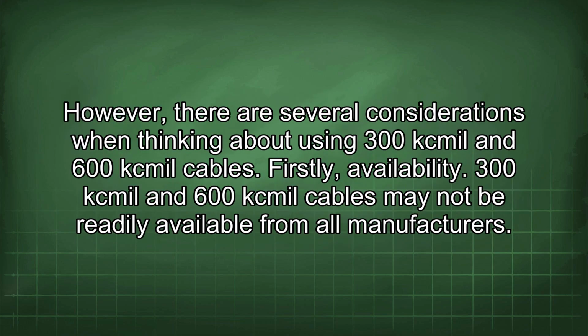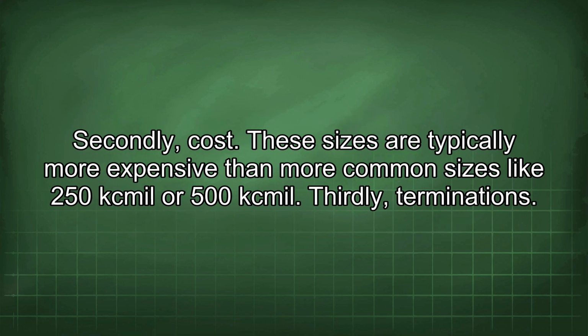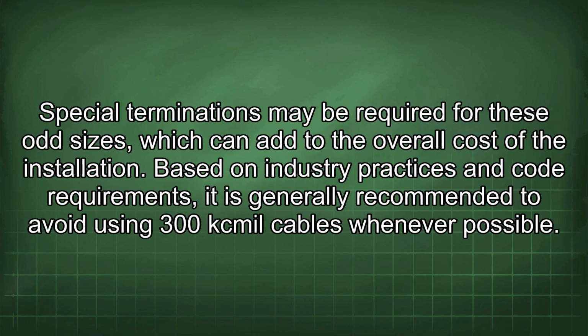However, there are several considerations when thinking about using 300kcmil and 600kcmil cables. Firstly, availability. 300kcmil and 600kcmil cables may not be readily available from all manufacturers. Secondly, cost. These sizes are typically more expensive than more common sizes like 250kcmil or 500kcmil. Thirdly, terminations. Special terminations may be required for these odd sizes, which can add to the overall cost of the installation.